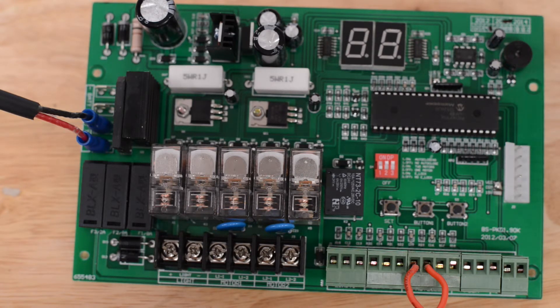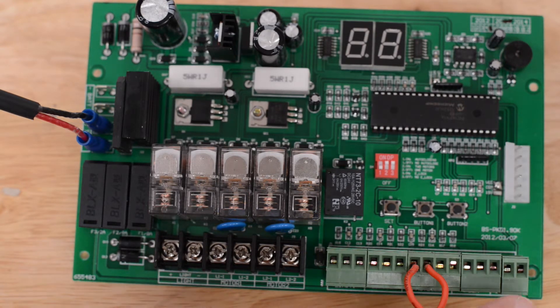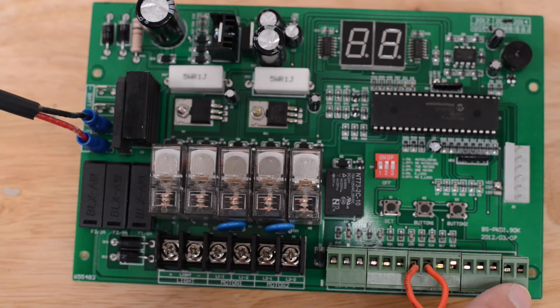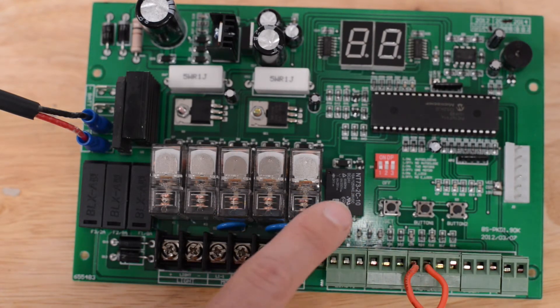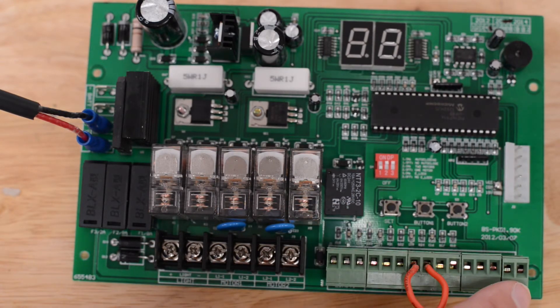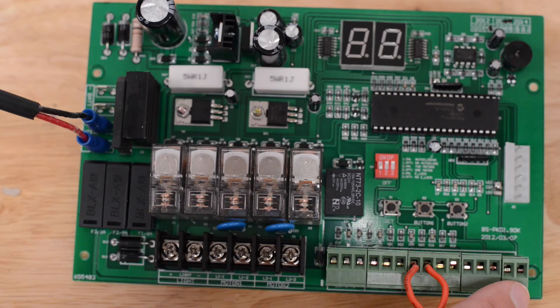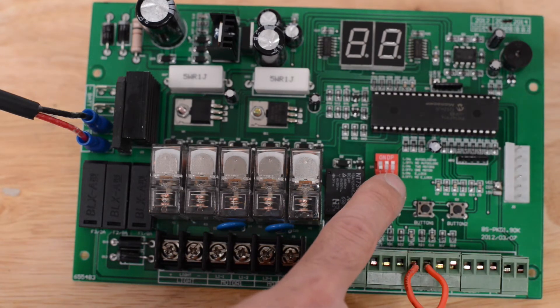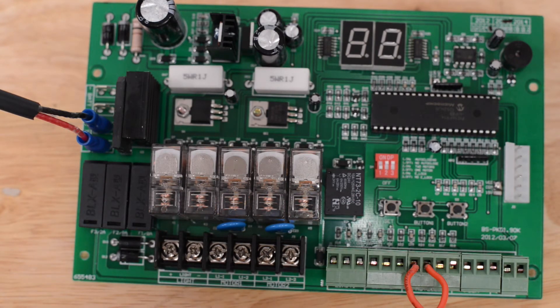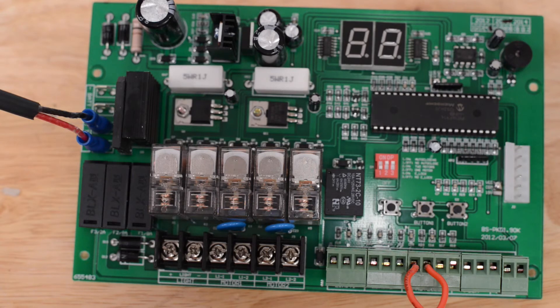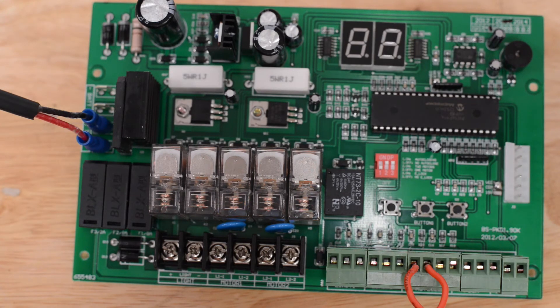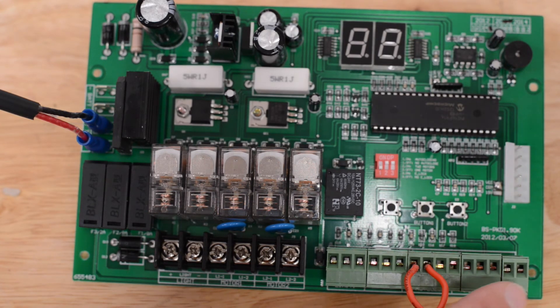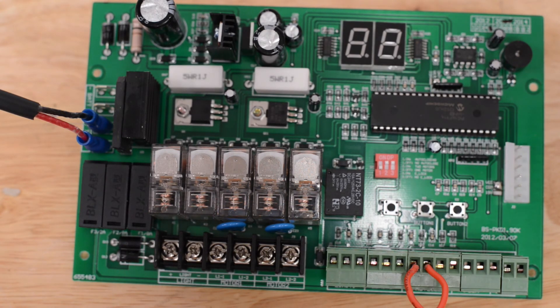Note before we mentioned that this terminal is where you would hook up a lock. In order for power to come out of this terminal, you must have dip switch three in the up or on position. If it is down, it will not put out any power through this terminal block.